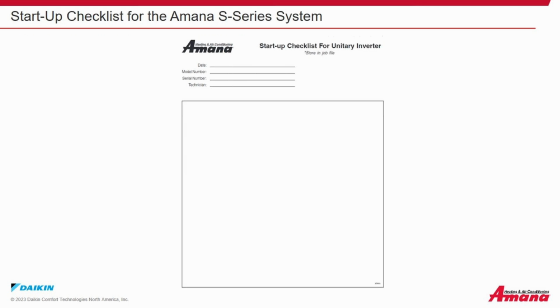Here's an example of a startup checklist for an Amana S-Series unitary inverter system. Pre-startup. Verify all packaging material has been removed. Remove all shipping brackets per installation instructions. Verify the job site voltage agrees with the unit serial plate. Verify condensate connection is installed per installation instructions.